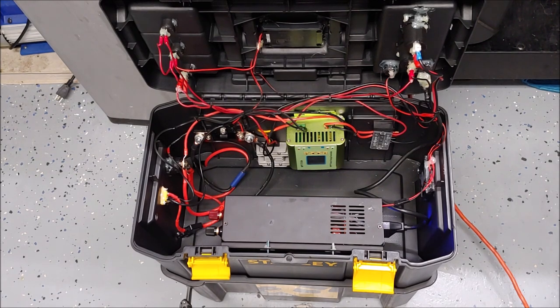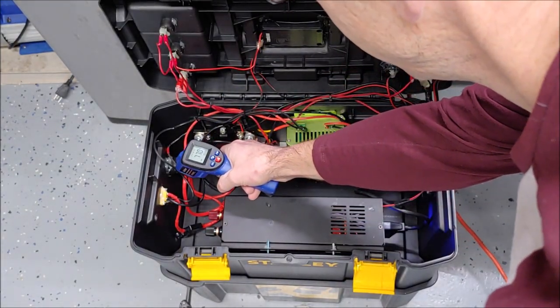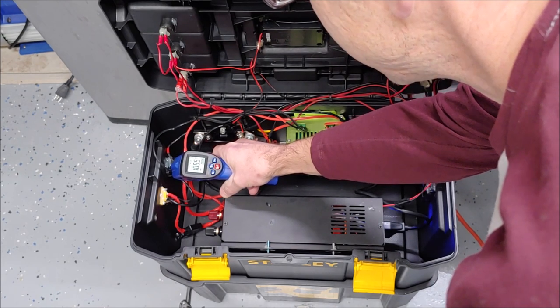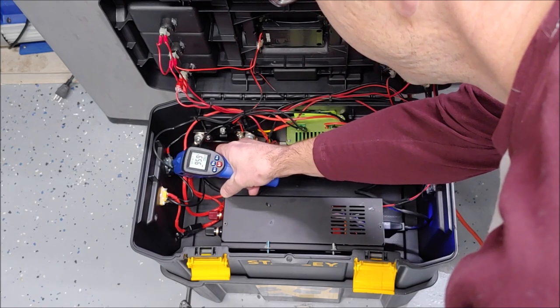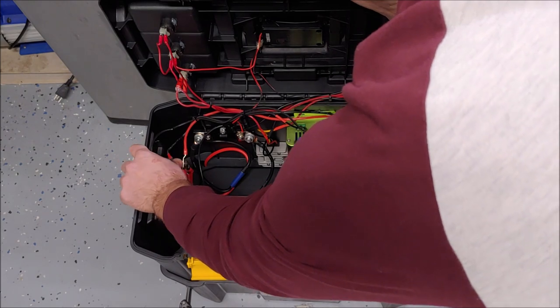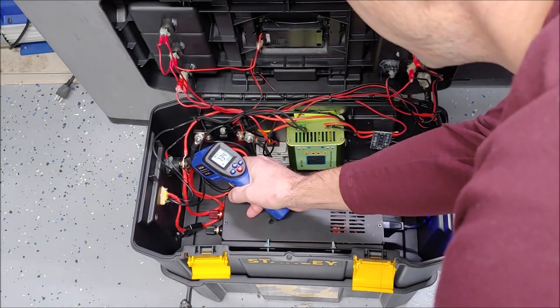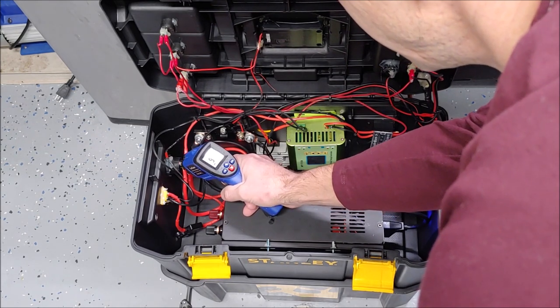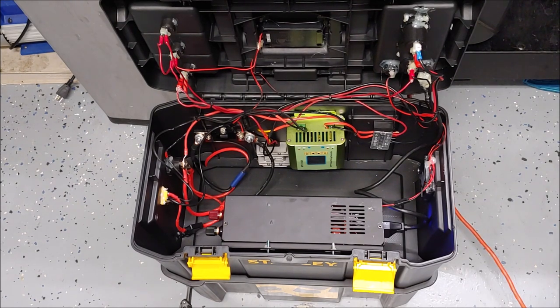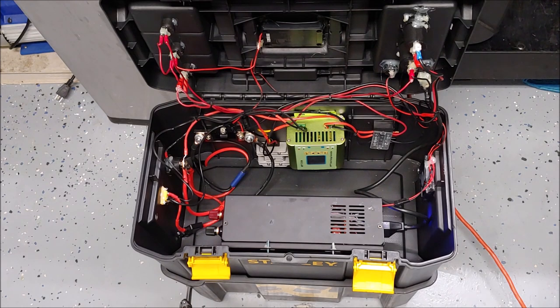Okay, I can tell you that we are hot enough to almost burn me. Let's see if we can find that hot spot with this heat gun. 100, 103, 106, 110... 113. Yeah, I saw 113 right there. So after just about three or four minutes of running, we are hitting 113 plus degrees on the switch and it's only going to get hotter. So this switch is not cutting it.